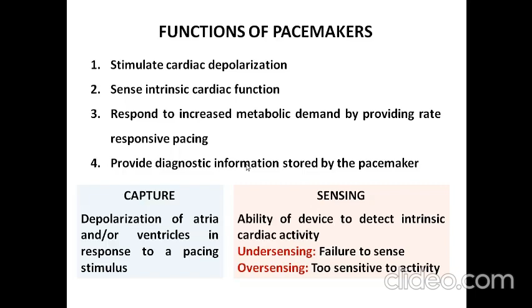And the concept of what is called capture in pacemaker function is nothing but depolarization of the atria or ventricles in response to a pacing stimulus. So it is the process of how the electric signals are imposed on the heart and how it responds to the application of the stimulus. That is called the capture area. Whereas sensing is the ability of the device to detect intrinsic cardiac activity. If the system is under sensing, it means failure to sense the cardiac activity. Whereas if it is over sensing, it means it is too sensitive to cardiac activity.